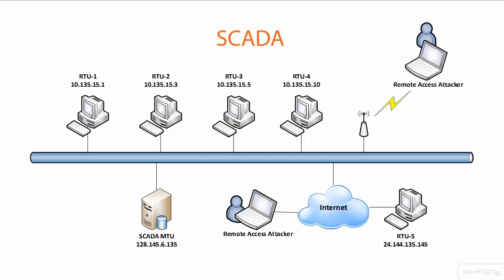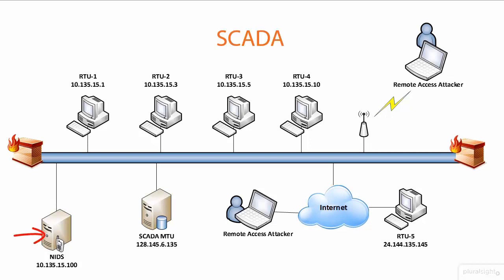One security approach: if SCADA terminals cannot be updated or patched, we wouldn't be able to apply a host-based intrusion detection system directly. However, we could deploy a network-based intrusion detection system. We can firewall off the network itself and put a network intrusion detection system in place so that if any attacker comes in remotely or attaches to the network, we can detect that intrusion.